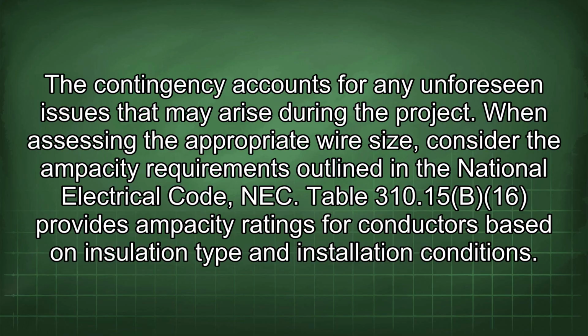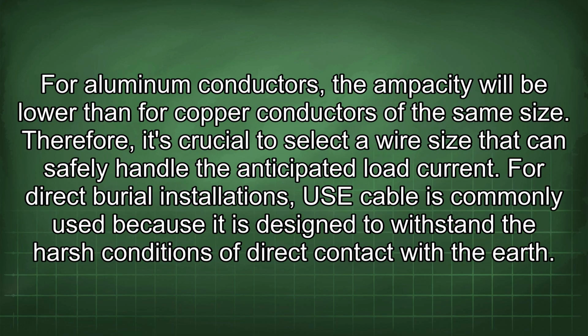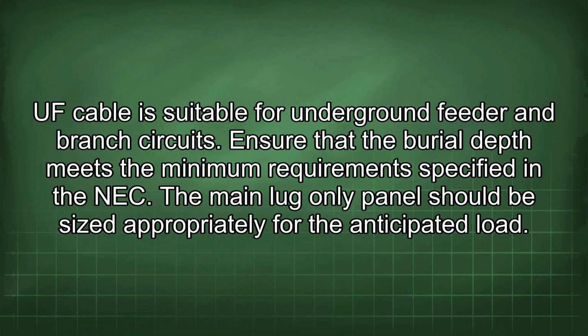When assessing the appropriate wire size, consider the ampacity requirements outlined in the National Electrical Code, NEC. Table 310.15(B)(16) provides ampacity ratings for conductors based on insulation type and installation conditions. For aluminum conductors, the ampacity will be lower than for copper conductors of the same size. Therefore, it's crucial to select a wire size that can safely handle the anticipated load current. For direct burial installations, USE cable is commonly used because it is designed to withstand the harsh conditions of direct contact with the earth. UF cable is suitable for underground feeder and branch circuits. Ensure that the burial depth meets the minimum requirements specified in the NEC.